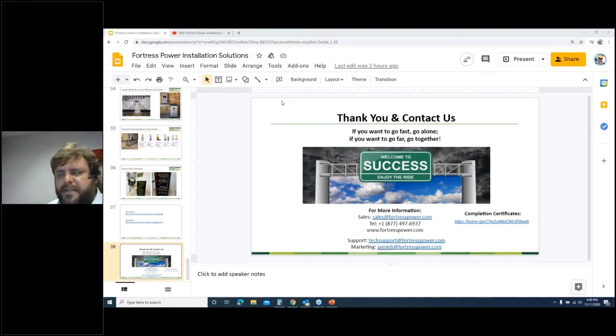It's not a coincidence that the eVault is 18.5 kilowatt hours. That's well sized for an 8 kilowatt battery inverter. But like I said, it's not always the case. So for example, we are officially supporting closed loop communication between Fortress and the eflex, and the Fortress is an 8 kilowatt inverter, and we put 2 eflexes on it, which is 10 or 11 kilowatt hours of batteries.